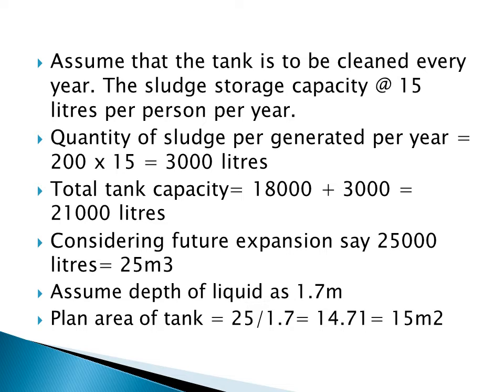Considering future expansion, we add some additional capacity. You can take 25,000 liters, which equals 25 cubic meters. When solving for university exams without considering future expansion, you can proceed with 21,000 liters. Practically, when designing a tank you should consider the future. Here we are taking 25,000 liters, which equals 25 cubic meters, considering future expansion.